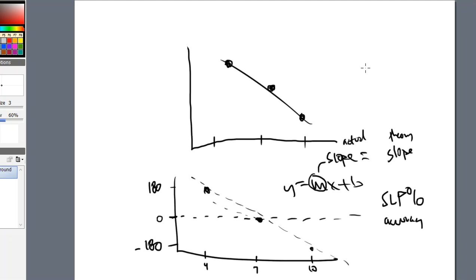So what happens very often is that we will take the actual and divide it by the theoretical and multiply by 100. So this will let us know, is it 95% good? Is it 100% good? Is it 97% good? And that's the kind of thing that we're after here. So the closer these 2 numbers are, the less error we have. And if we have less error, then that means it's reading what it should be reading over the course of the calibration.